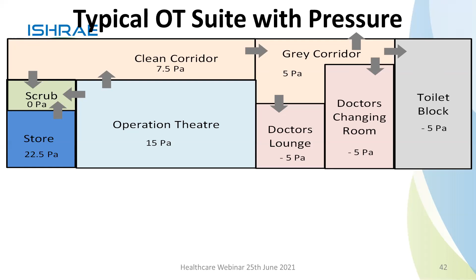You don't want the operation theater instruments to be having any contamination. So that is at the highest pressure. Then the operation theater is at 15 pascals. Then the scrub is where they clean the foot and all that. That is at 0 pascals. That's a dirty area. Then you've got the clean corridor, which is at 7.5. Then there is a gray corridor. Then there is a doctor's lounge, doctor's changing room, and then the toilet block. You can see that progressively the air is moving outwards towards the toilets and the changing rooms.